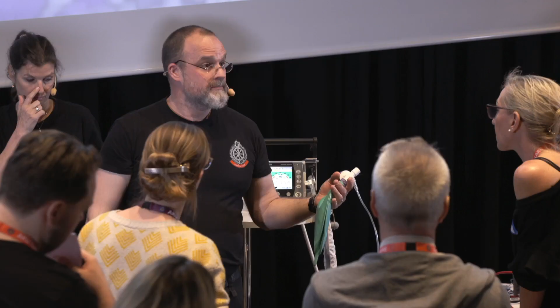So you're taking the passive mode, and with fully automated CPR, with this ventilator, you're turning it into an active mode. And so you are reversing the effects of the compression on the inhalation. You can hear, as you compress, gas is going in at 205 milliseconds during the downstroke, and gas is escaping. You can see there CO2, well, the CO2 is not coming out on that one. It's not exact science, guys, because I'm actually controlling CO2 from a little bobble over here. All right?